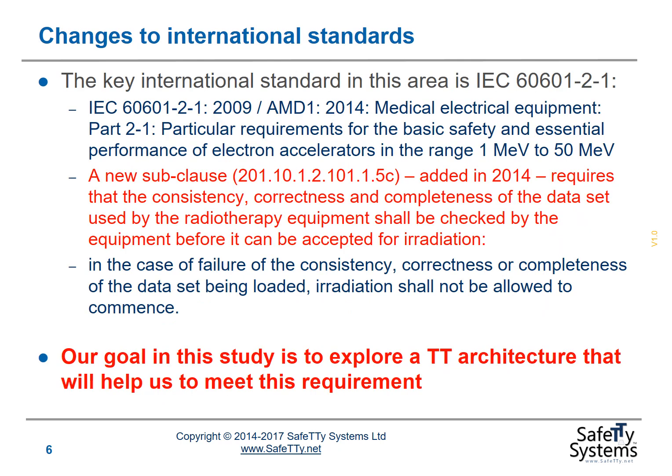The key international standard in this area is IEC 60601-2-1. This standard applies to this kind of medical equipment that includes electron accelerators.